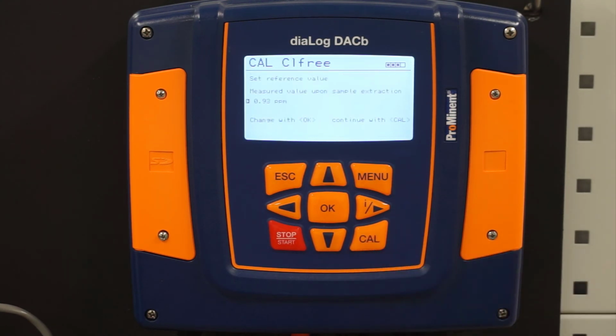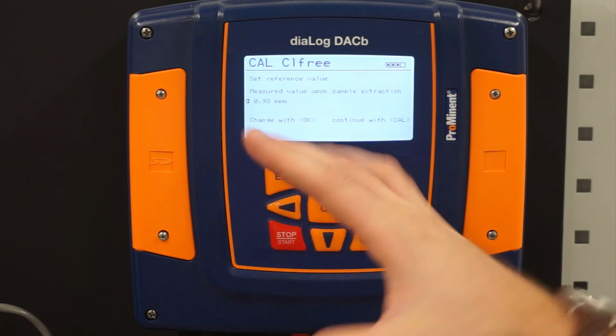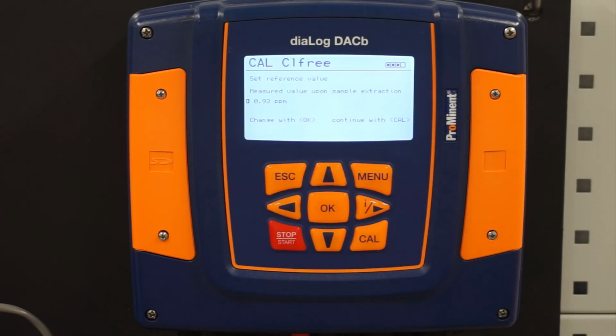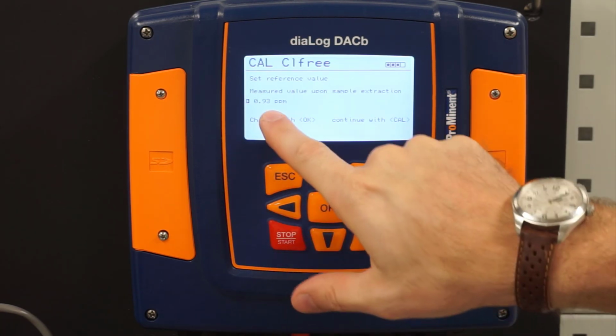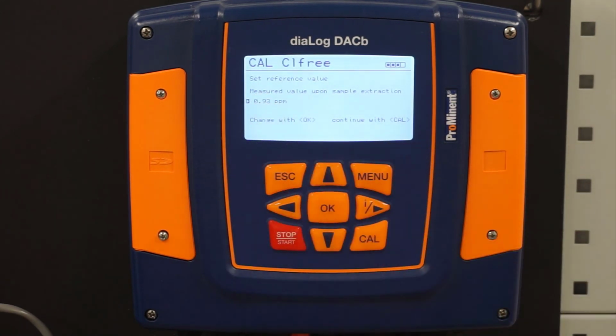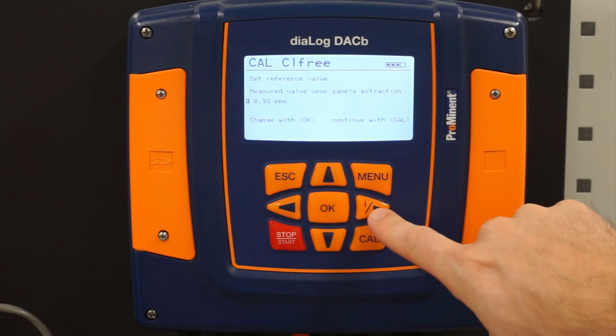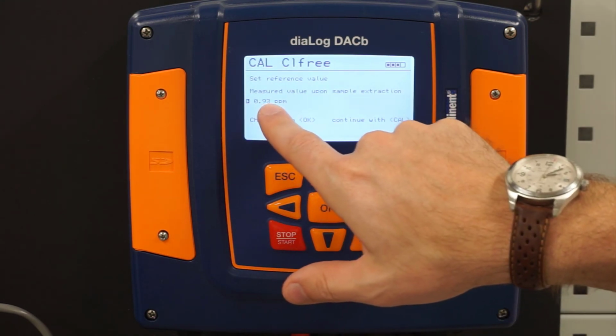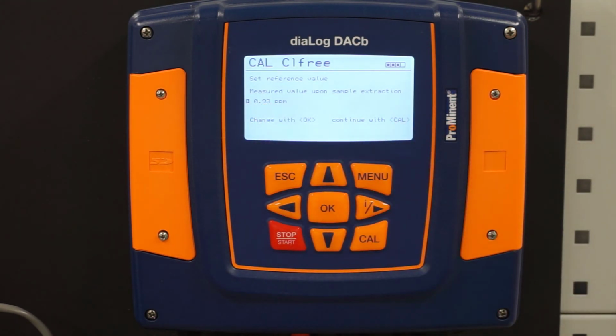Once we do that, we have the sample. As soon as I hit continue cal, it locks that number in. So now I have time to go do my DPD test. Once I've finished my DPD test, here's what it thinks it's reading, and I have to determine what the actual DPD test told me it was. So let's say it was actually 0.90. Let's say that's what my DPD test showed.